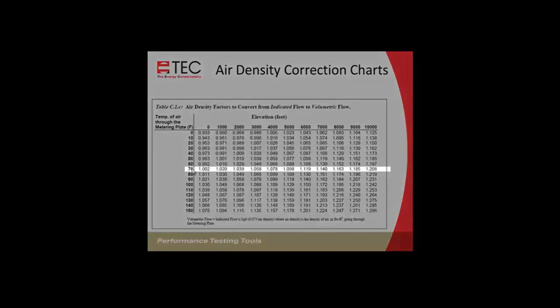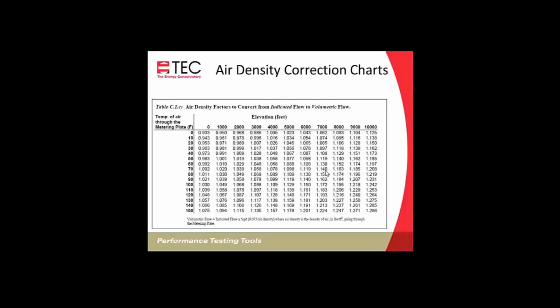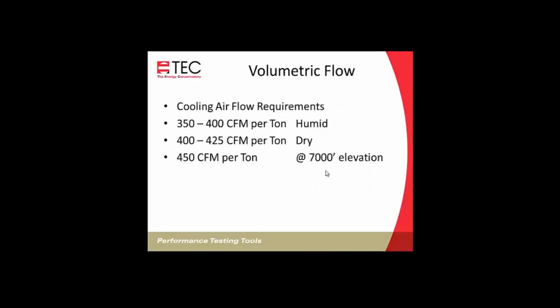And let's say we're at 70 degrees and 7,000 feet of elevation. Now we're up to about a 14% difference. So multiply it by 1.14 to get our actual volumetric flow. And here are some volumetric flow recommendations. If you're in a humid climate, humid air can take on more energy than dry air, so you need less airflow. So between 350 and 400 CFM per ton. If you're in dry climates, you're going to need more airflow, somewhere between 400 and 425 per ton. And if you're at 7,000 feet of elevation, you're going to need about 450 CFM per ton. And that's if you've made that adjustment for volumetric flow.